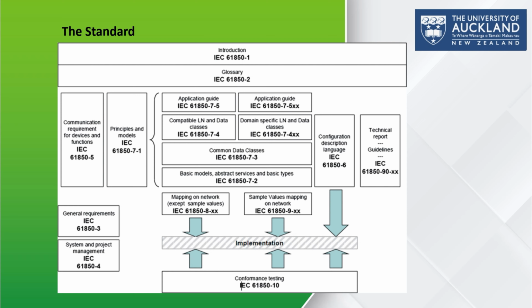extend these concepts. For system configuration, IEC 61850-6 defines the substation configuration language, that is SCL. Technical reports and guidelines under IEC 61850-90 provide further clarification and advanced use cases. Communication mappings to actual network protocols are provided in IEC 61850-8 for general messages and IEC 61850-9 for sample values. This mapping supports real-world implementation of the standard in devices and networks, right?